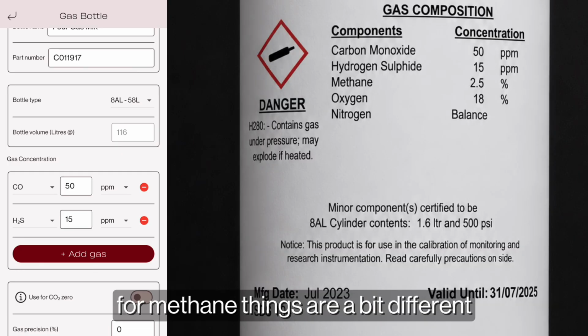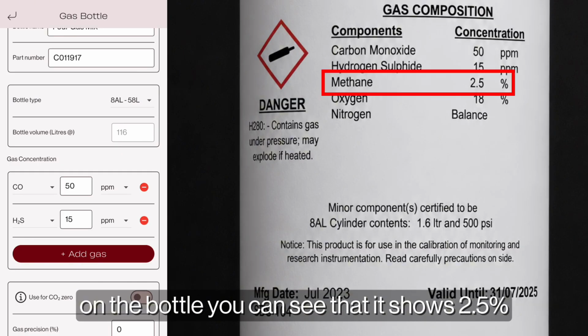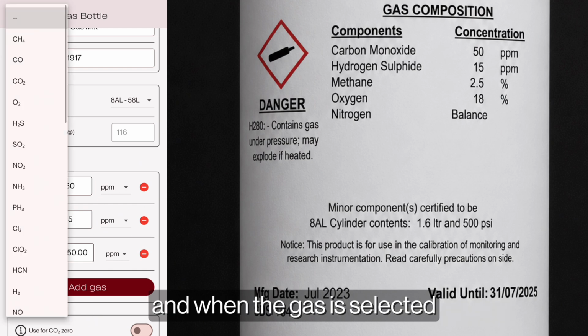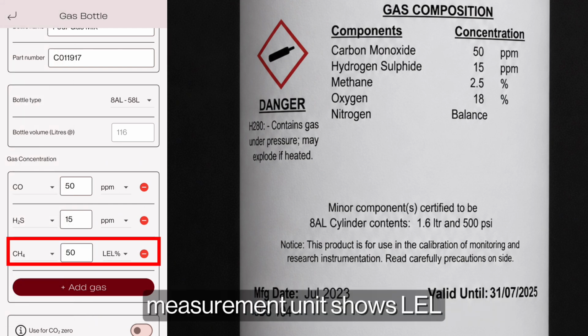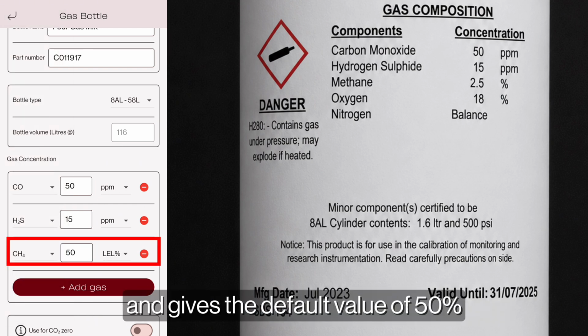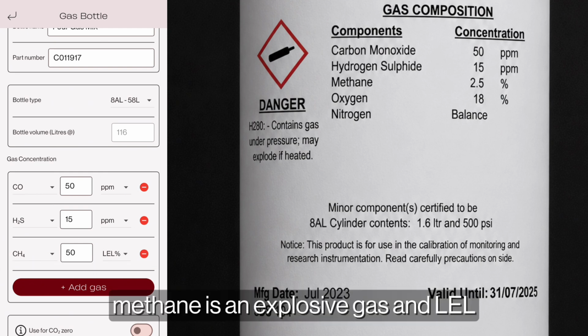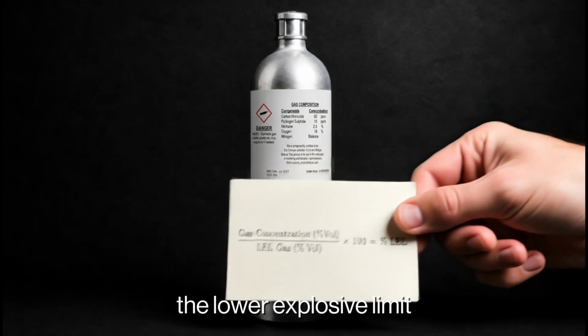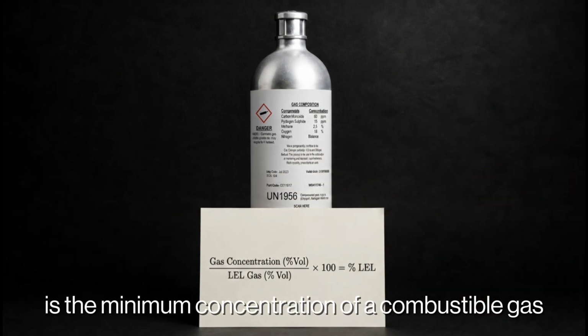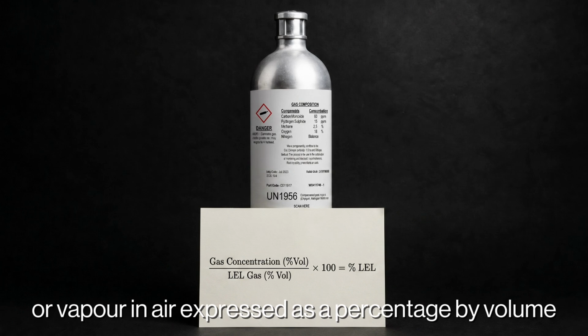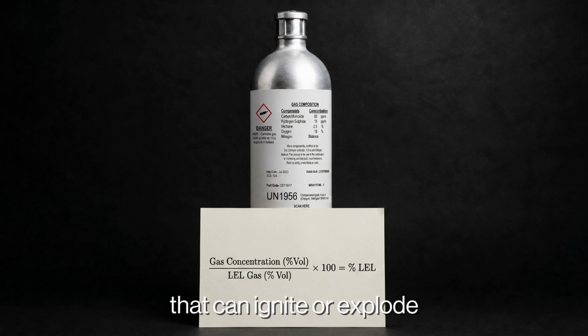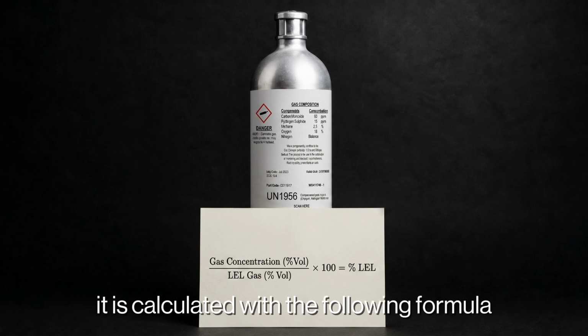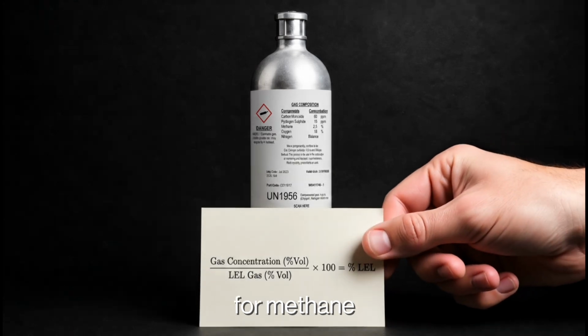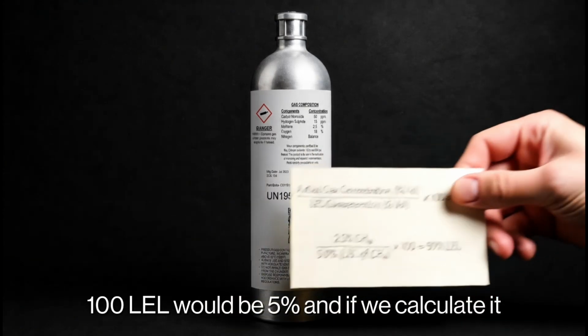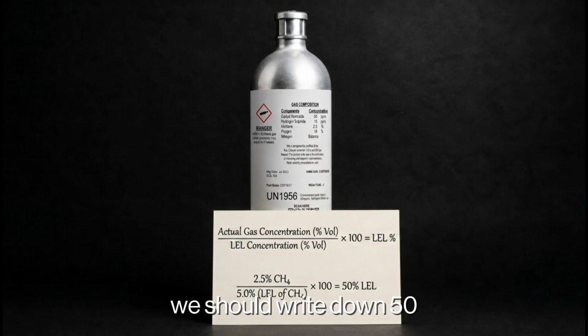For methane, things are a bit different. On the bottle you can see that it shows 2.5%, and when the gas is selected, the measurement unit shows LEL and gives the default value of 50%. Methane is an explosive gas, and LEL, the lower explosive limit, is the minimum concentration of a combustible gas or vapour in air, expressed as a percentage by volume, that can ignite or explode. It is calculated with the following formula. For methane, 100 LEL would be 5%, and if we calculate it, we should write down 50.